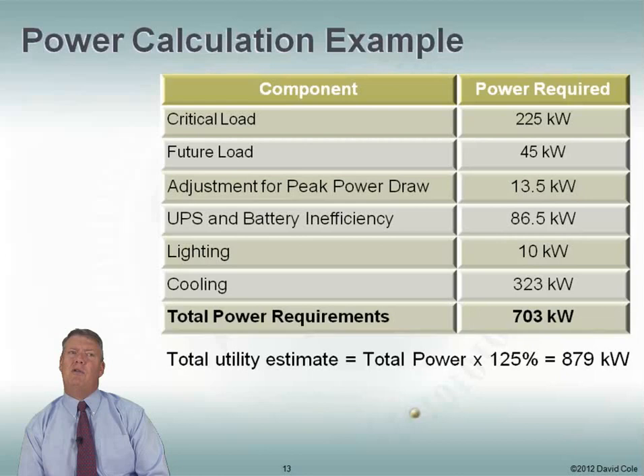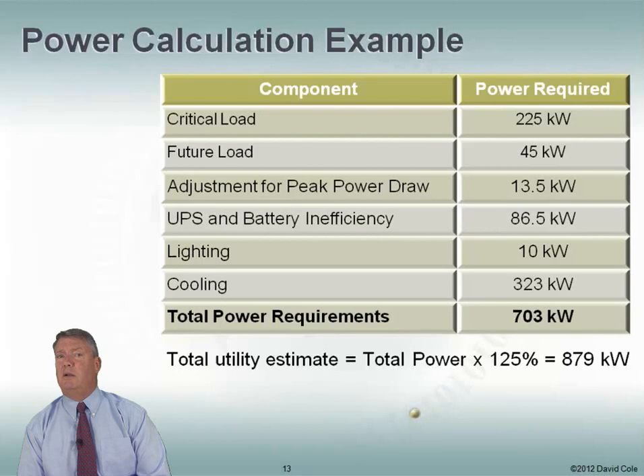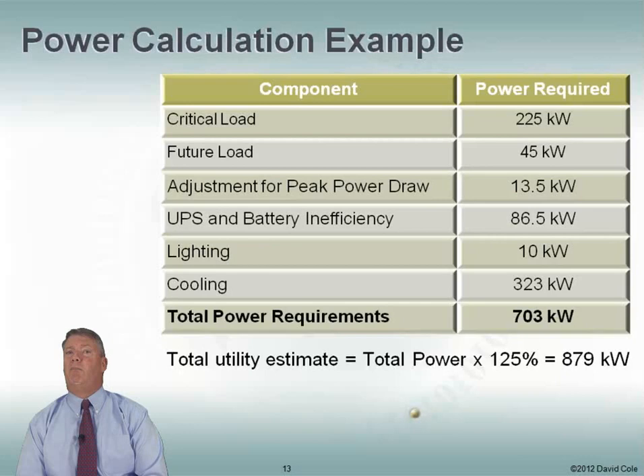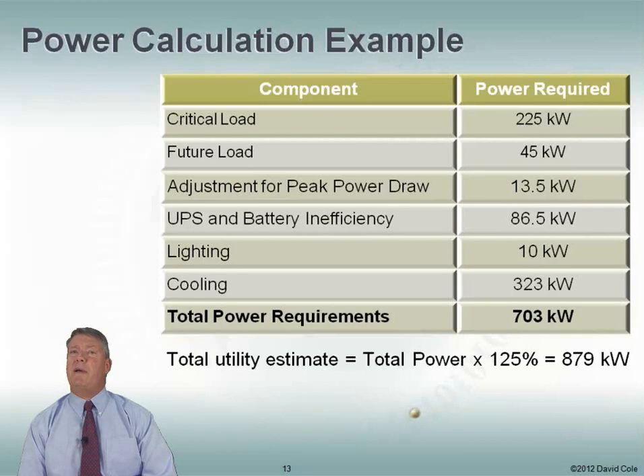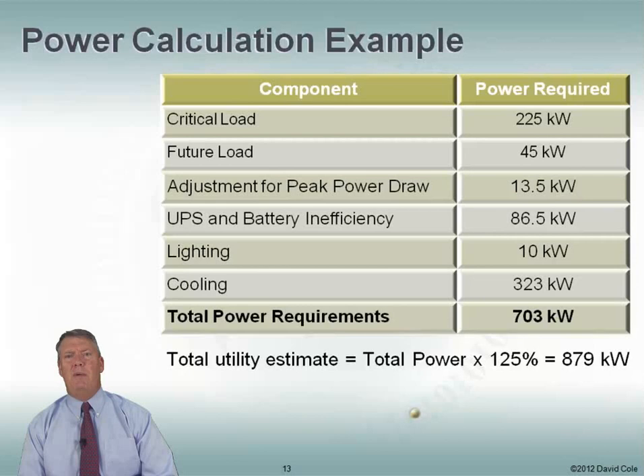How much do I need to tell the utility company? I can't tell them 703 kilowatts, because I never want to use more than 80% of what they give me — I want that 20% overhead according to the National Electric Code. So I take my total power of 703 kilowatts and multiply by another 25%. That means I need to tell the utility company I need 879 kilowatts. Way back we started with 225 kilowatts for our critical load, and now we're at nearly four times that.